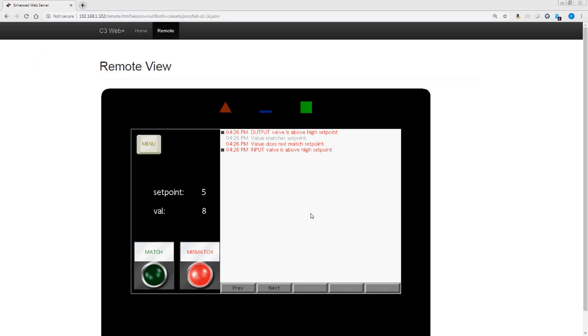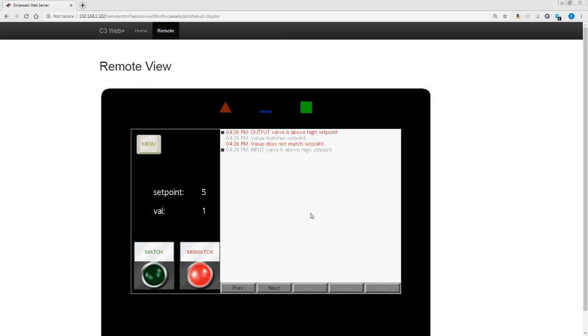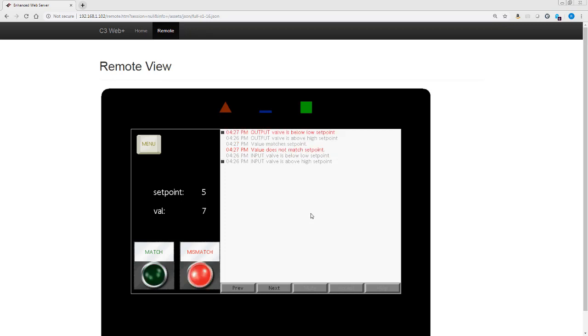So on this screen, this is our original screen. We can see there are a lot of different things going on. The gray means an inactive wait accepted alarm, so the alarm condition occurred, it is no longer current, however we are letting the operator know that it exists. Now you can see everything is red or gray and that's it.